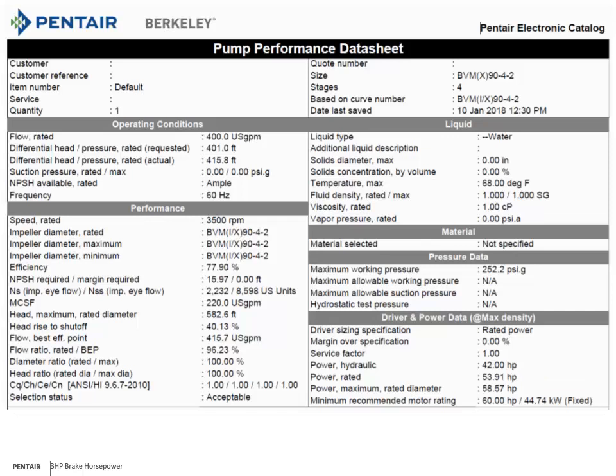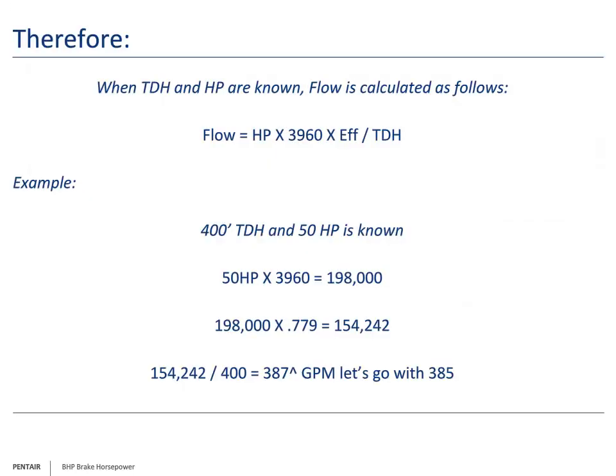Reviewing the data in a sizing program shows us our best option is still more horsepower than would be allowed. So we now have a better target number for efficiency. Let's recalculate at a lower gallons per minute. Using the 77.9% efficiency, we can recalculate the flow and discover we should be able to flow 385 gallons per minute. We could then go to the sizing program to see if we hit our target horsepower.